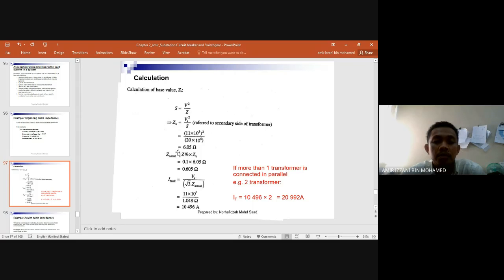In order to get the actual impedance, Z base is the base value. If you forget about this, you can refer to the EPS notes, electrical power system. So Z actual equals Z pu times Z base. The pu is in per unit here. So just multiply 0.1 by 6.05 ohms, and we get 0.605 ohm. Then we can determine the fault current, which is Vs over square root 3 times Z actual. All the values are available here. We use the values and get the fault current as 10496 amperes.